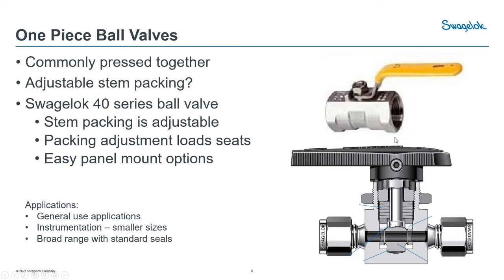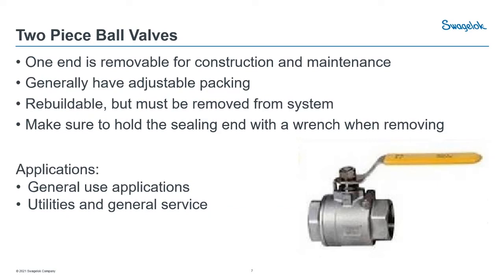From one-piece, we move into the two-piece ball valve. One nice thing is most of the body is solid in one piece, with the exception of one end that unthreads. You can see a seam where that piece can be loosened and removed — that's how construction happens. You load the ball and seals in on that side and adjust to get the correct preload on your packing. This allows you to rebuild that valve, though you have to isolate and physically remove it from your system to take that end cap off.